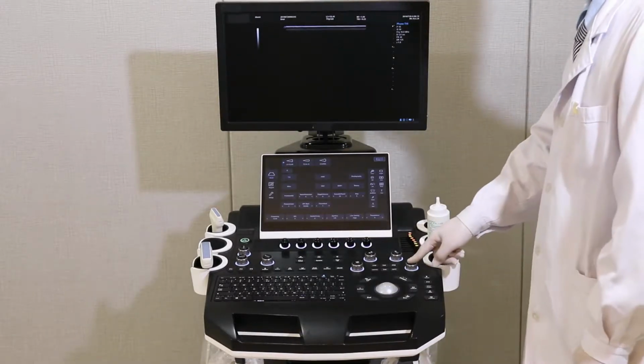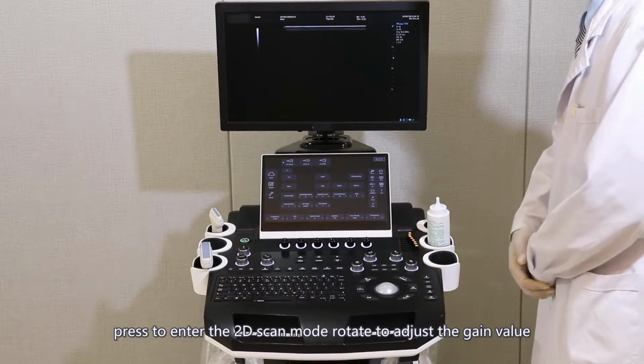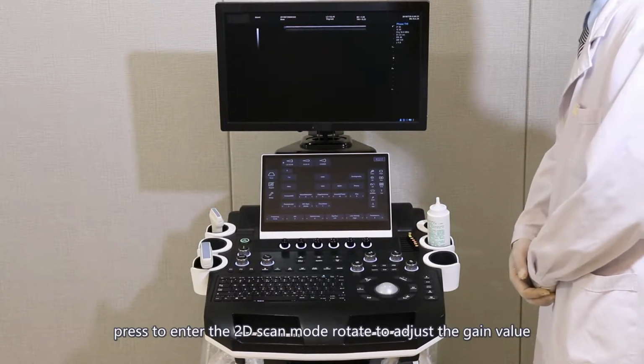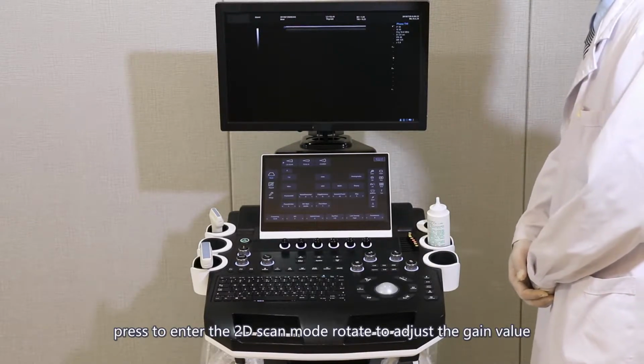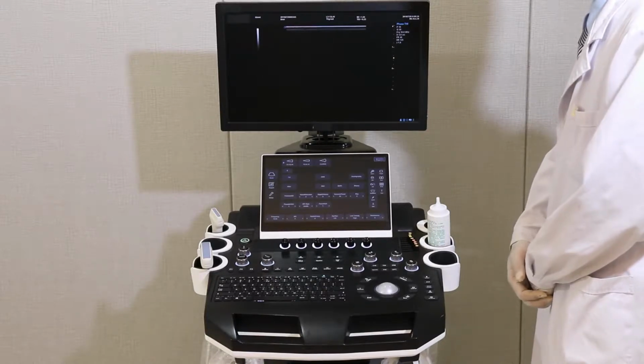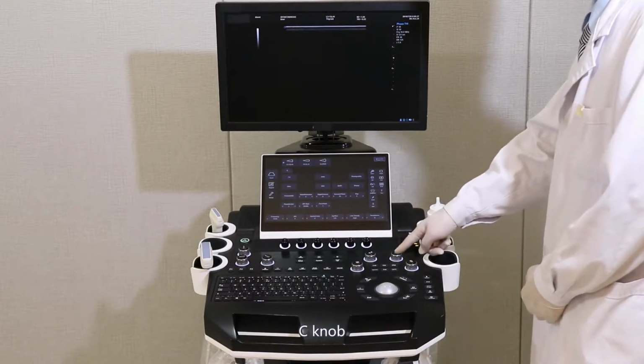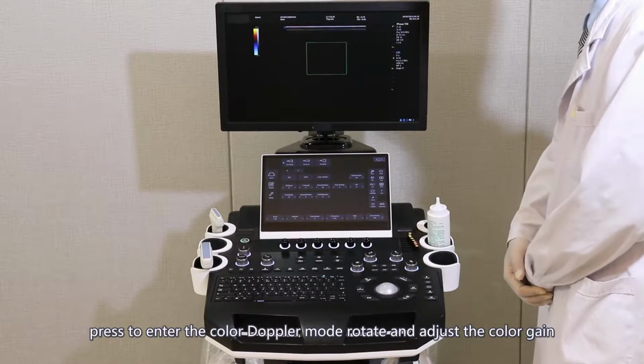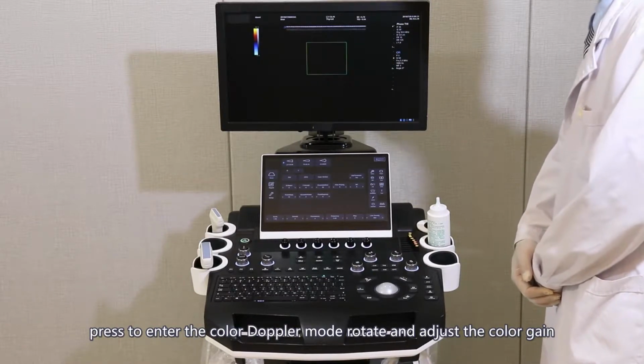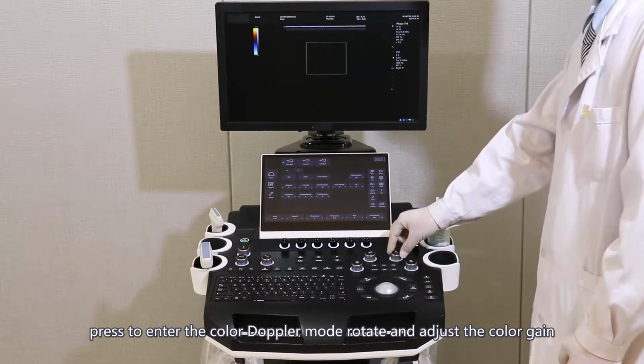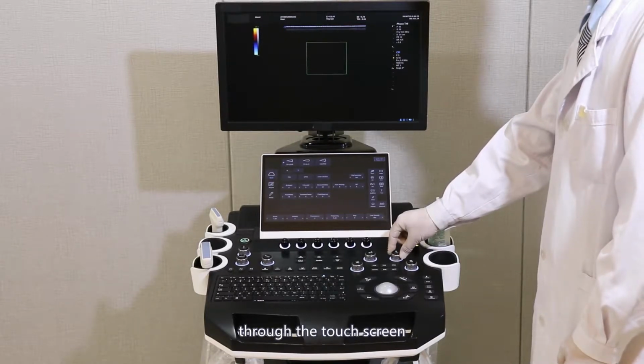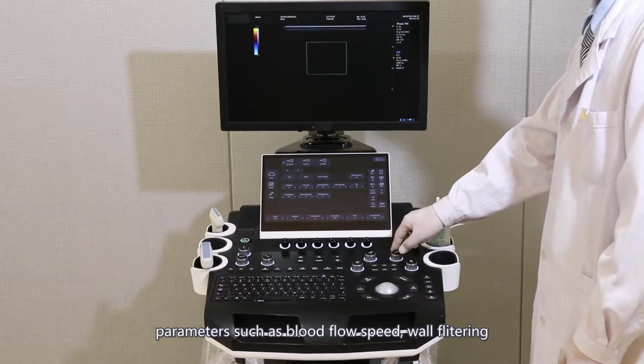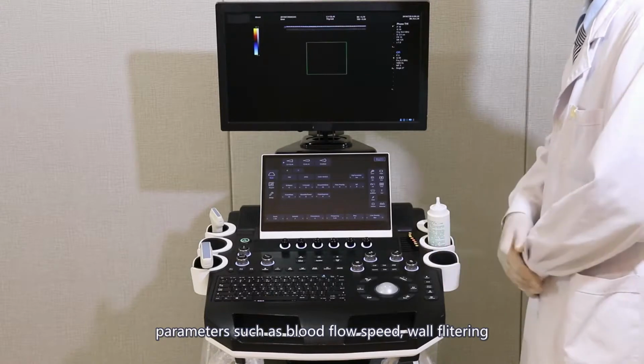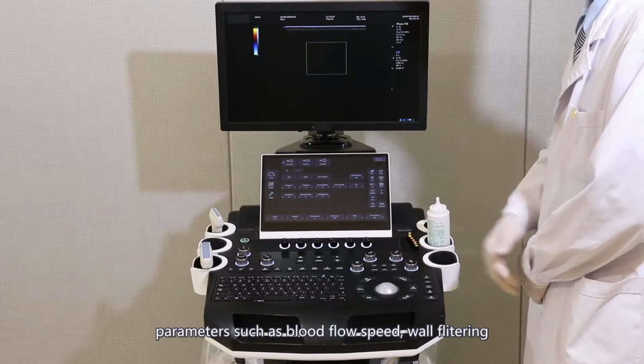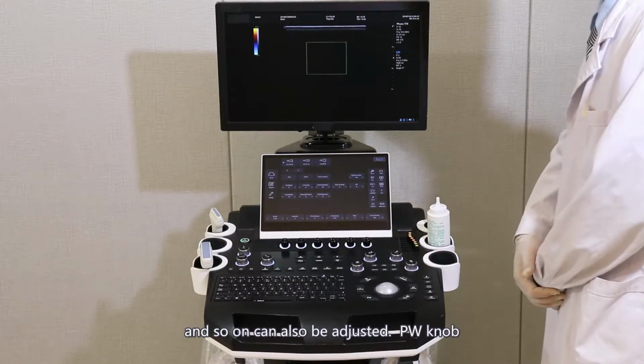B knob. Press to enter the 2D scan mode. Rotate to adjust the gain value. C knob. Press to enter the color Doppler mode. Rotate and adjust the color gain. Through the touch screen, parameters such as blood flow speed, wall filtering, and so on can also be adjusted.